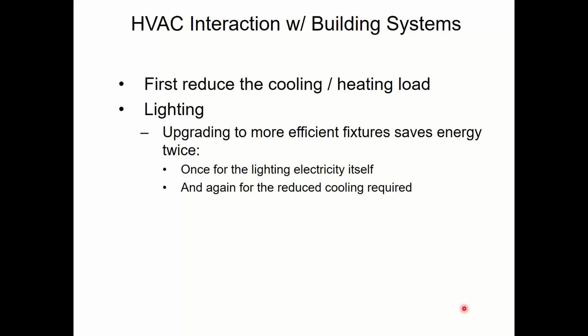Because if you didn't know it, when we do load calculations, which is what we call the heat loss, heat gain calculation of the building to figure out how much heating and cooling it gains and loses during various times of the year. For cooling, we do that calculation on a summer day, sometime in the afternoon, at a peak scenario when it's very hot outside, like 91 degrees or something like that. And we'll go through that more in a little bit. But that's my cooling scenario. Every person's in the building, every light's on, the sun's beating on the building, it's the hottest day of the year. Then I calculate my cooling.